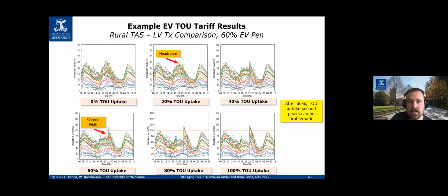And what we can see is that, immediately at 20%, we see a slight reduction in that peak, which we expect as 20% of customers start shifting their demand to later. 40% is really where it starts to deviate. Yes, we get a larger headroom, but now we're starting to eat into the diversity that was there in the native use profiles. When we assume 40% of customers are going to charge within this window, 100% of those 40% are all going to start charging at pretty much the same time. That loss of diversification can be a big challenge for time of use.